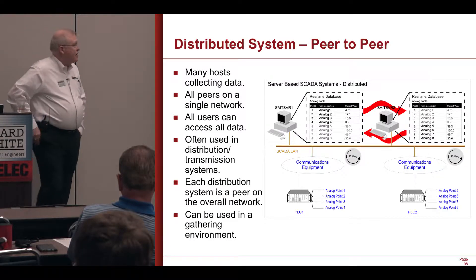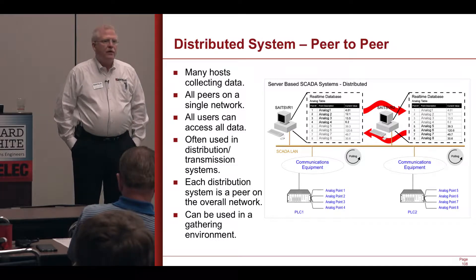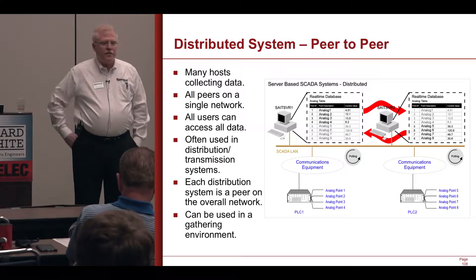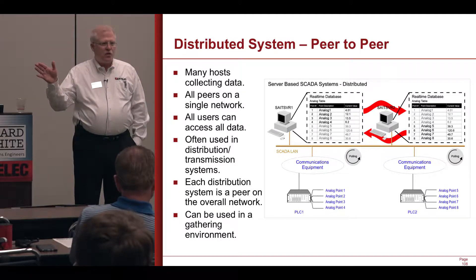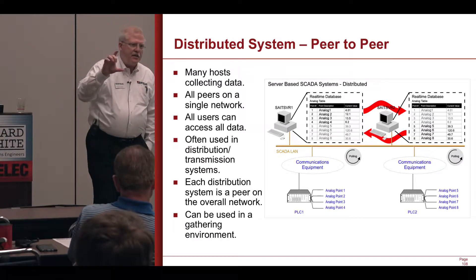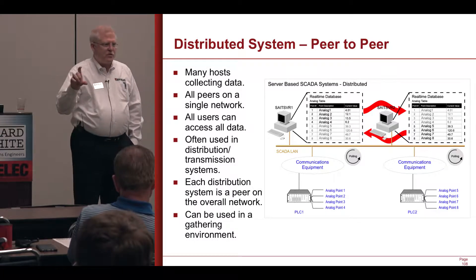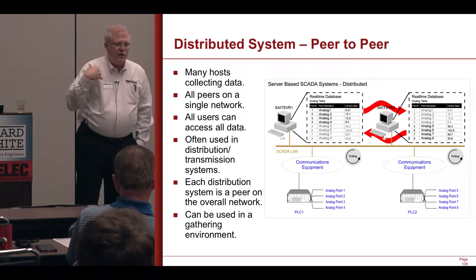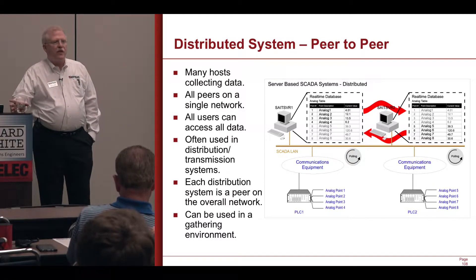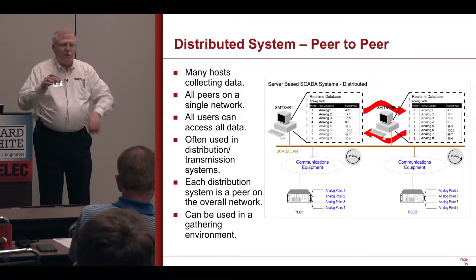The next kind of system would be what is called a distributed system or a peer-to-peer. Cygnet is a distributed system or peer-to-peer because I can have its polling server in multiple locations throughout my business, and any of the HMIs with connectivity can see any one of those polling servers, provided I have login credentials and capability. Cygnet is real popular in production facilities for that reason, because I can run it in the field and yet glue it together at the enterprise level.